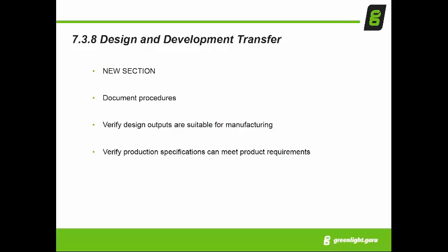Now, keep in mind in 820.30, the FDA design control regulations, there is a clause for design transfer. The good news is, again, that ISO 13485 and FDA are not going to be word for word, but the concepts and the expectations are identical. So design transfer, brand new to the ISO world. Now you need to have processes in place that describe the transition from development into production or into manufacturing.